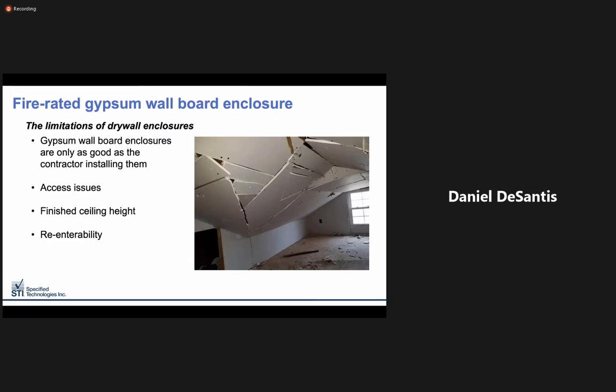Or maybe you have 500 linear feet of DAS cable to protect that snakes around the project. Access can be tough, especially in a city like New York where space is at a premium. Since a full depth shaft wall assembly must be built around all four sides of the protected item, you can lose finished ceiling height, and accessing the inside of the shaft for troubleshooting or upgrades can be problematic as well.